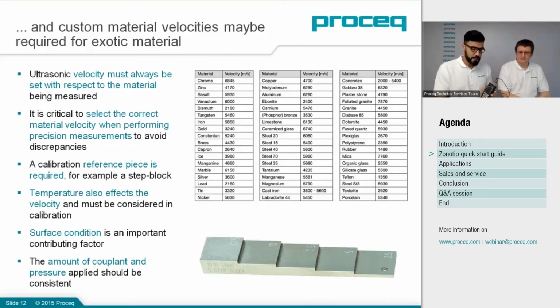One fairly common factor, which we were actually discussing a few days ago, is the amount of coupling paste applied on your reference sample and your real sample during the test, and also the pressure applied. That makes a difference - you can get up to 3 dB difference in the received amplitude, which is significant and will affect your thickness measurement to a large degree. So it's always good to consider these little side notes.